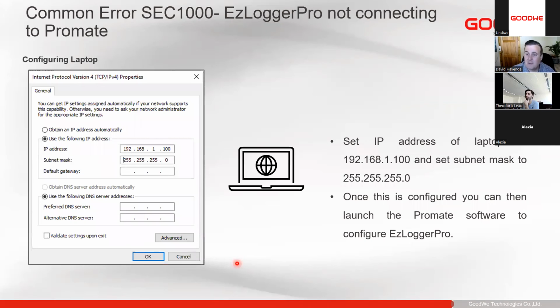Next, we need to configure our laptop, because we're doing a direct connection. We need to make sure our IP address on the laptop is also a fixed IP address. That will go under your internet settings, your IPv4 settings. You can just Google how to change your IP address for your current operating system, Windows 10, Windows 11. They're all slightly different. Then you go to your IPv4 settings and you set your IP address.